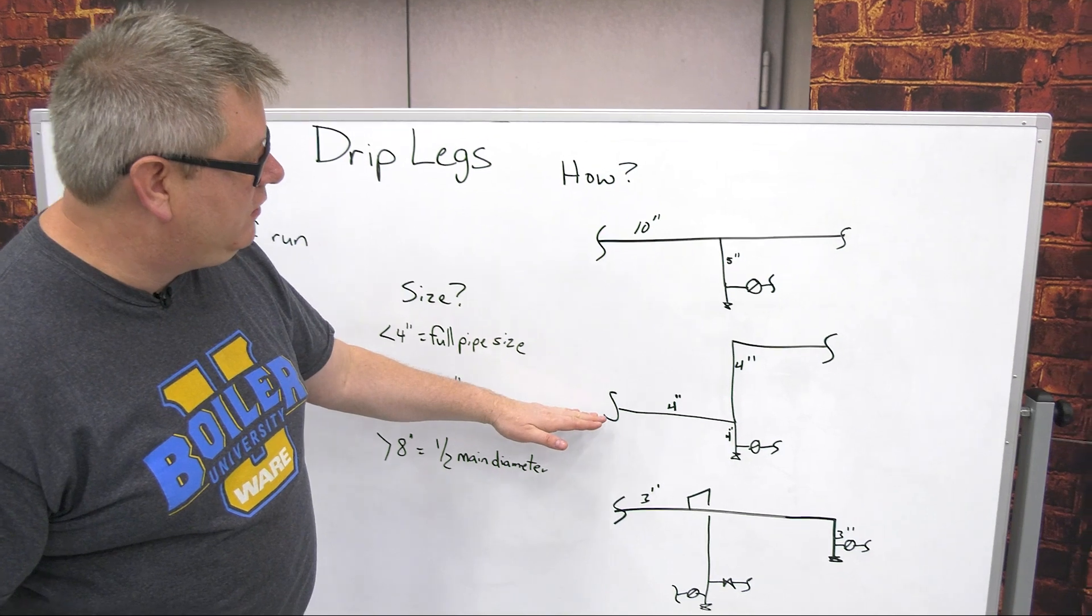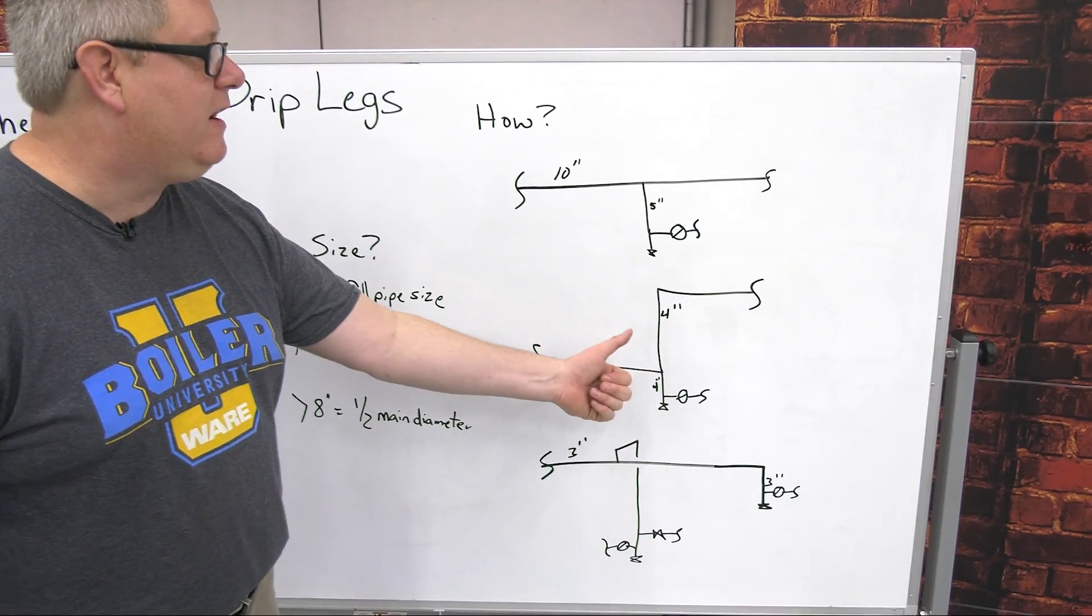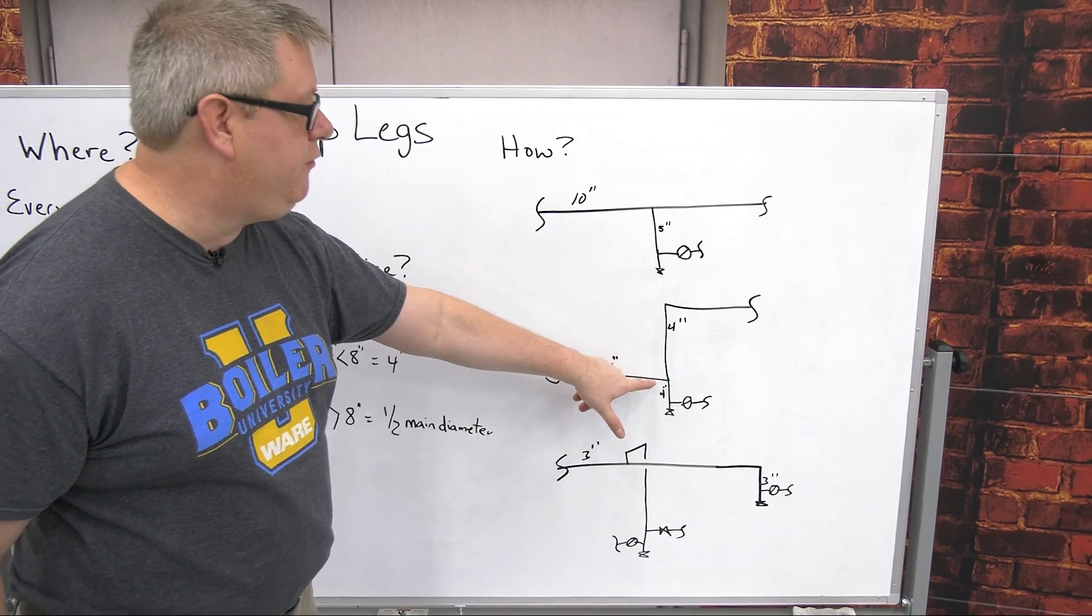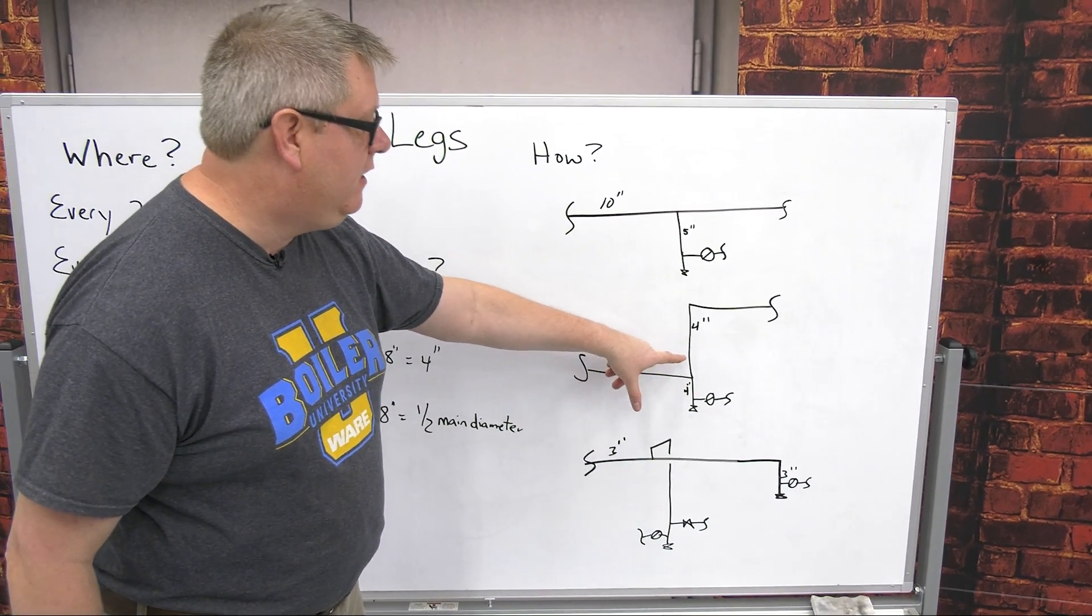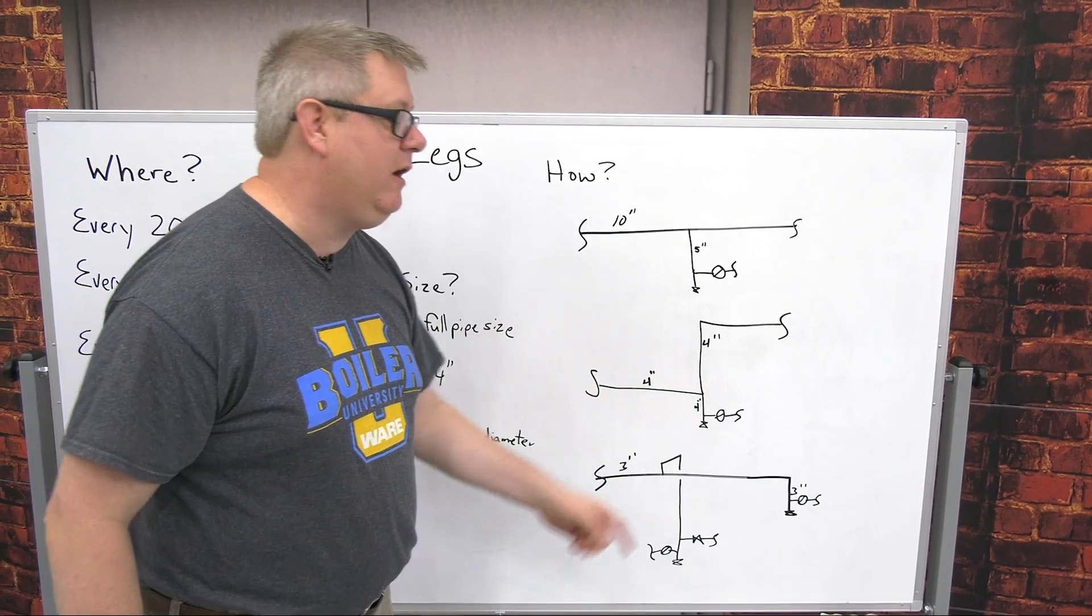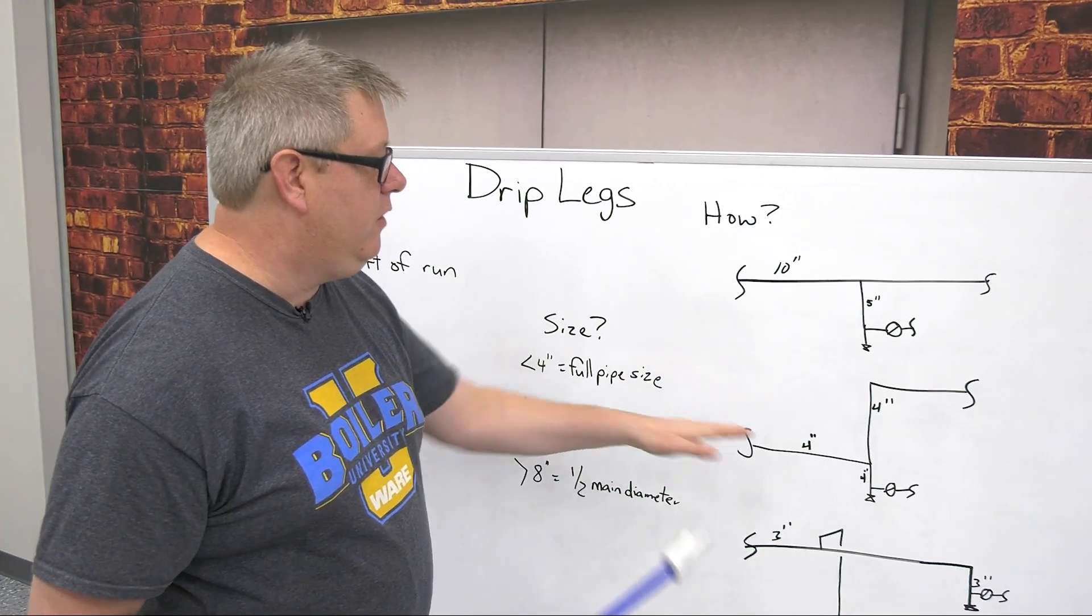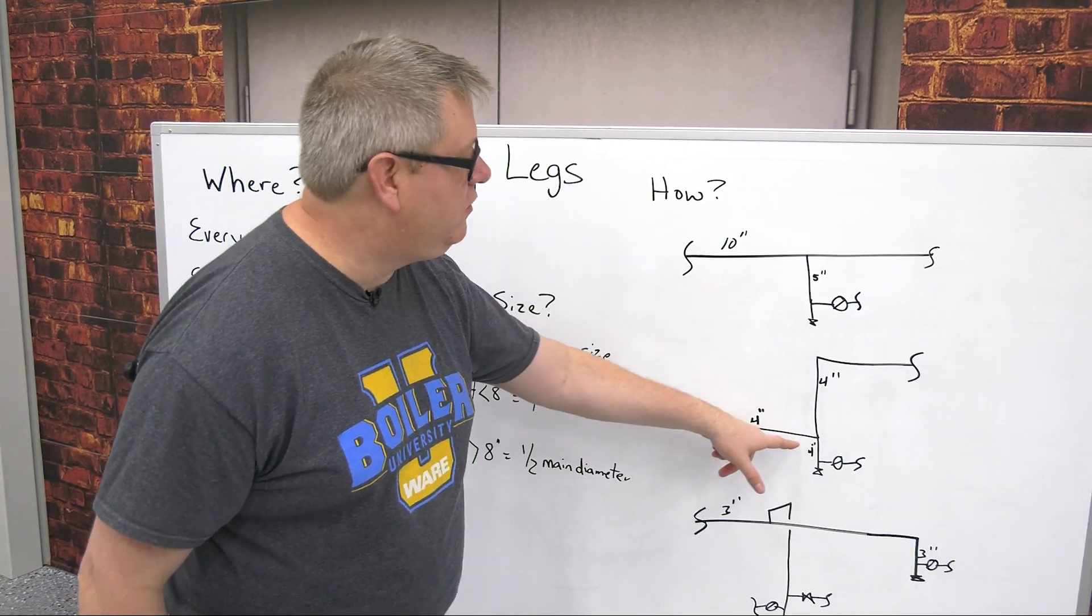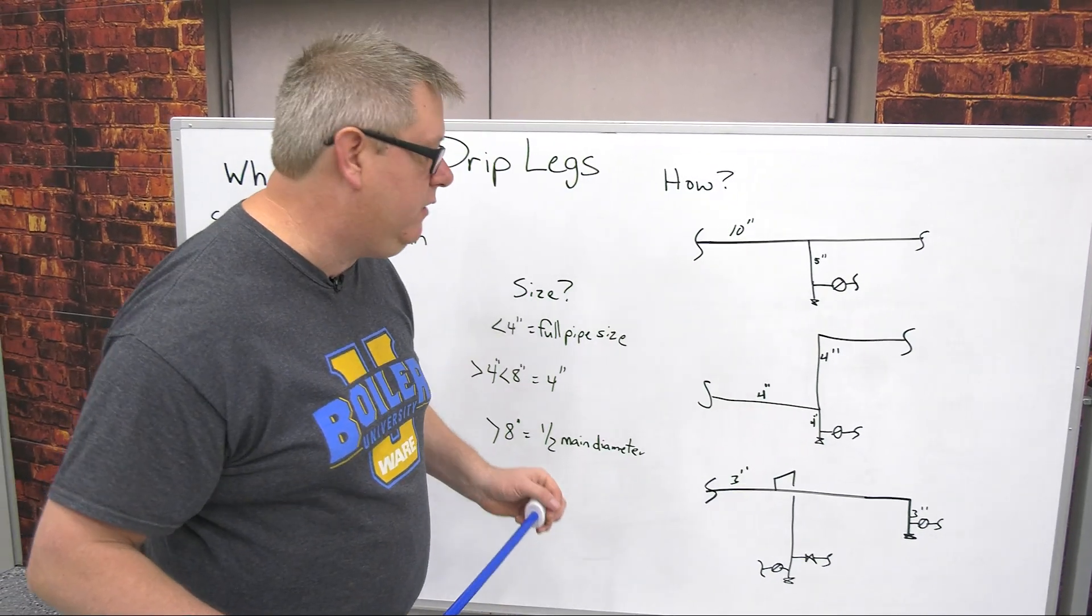If we've got an elevation, a steam line coming this way, that condensate's not going to want to go up. So we'll typically just put in a full size tee and come down, and once again out sideways to the trap with the drain line. And because this main is a four inch, it's going to continue in four inch and my drip leg is going to be four inch.